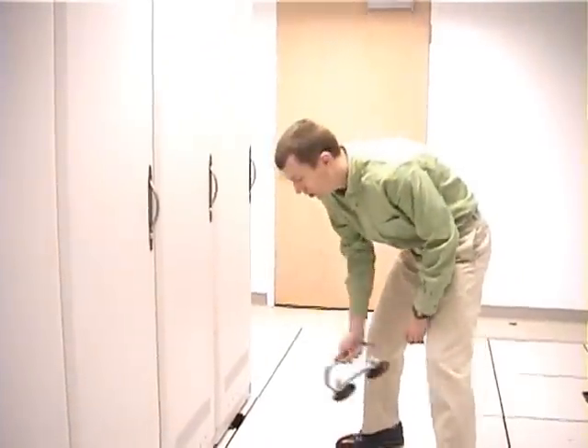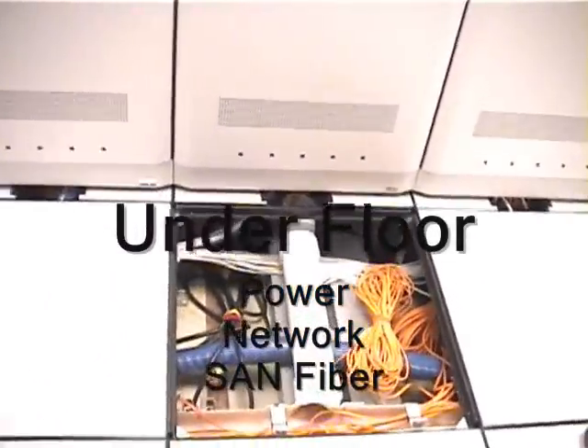As you can see here, standardized racks throughout the facility, with Liebert air conditioning units on either side. We're now going to walk towards the back and I'll show you underneath the raised floor. Here's the back of the cabinet — we've got our tile puller here. You can see what I was talking about earlier: how we jackhammered out the bottom of the floor, poured concrete, and then all of the electric and network cabling and fiber channel for our SAN storage array runs underneath the flooring.